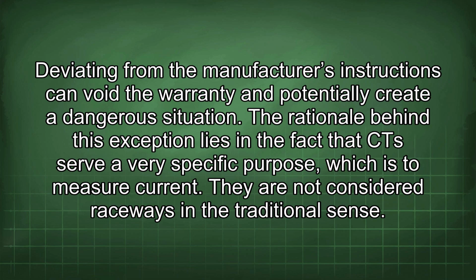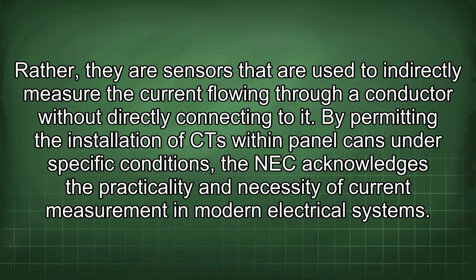The rationale behind this exception lies in the fact that CTs serve a very specific purpose, which is to measure current. They are not considered raceways in the traditional sense. Rather, they are sensors that are used to indirectly measure the current flowing through a conductor without directly connecting to it. By permitting the installation of CT within panel cans under specific conditions, the NEC acknowledges the practicality and necessity of current measurement in modern electrical systems.